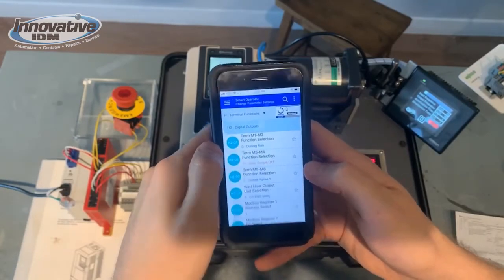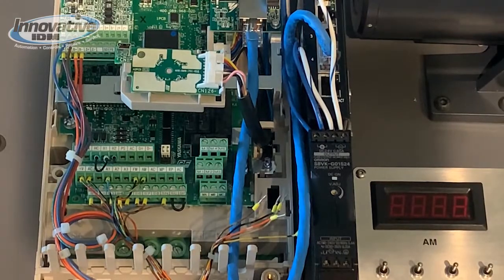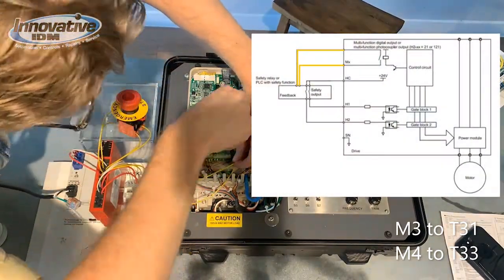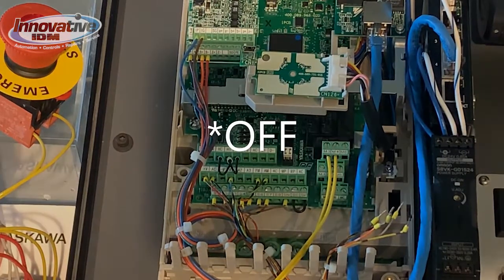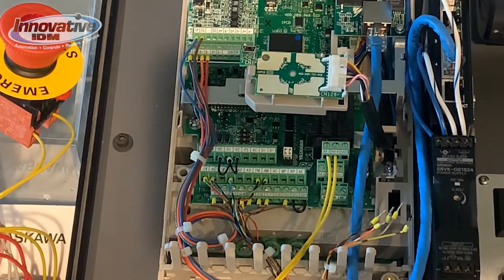Now it's time to wire. Here you can find terminals M3 and M4. Here on the drive we can see our Safe Torque Off inputs — as you can tell, they're jumpered together. If you set this drive up for Safe Torque Off, make sure to not lose that jumper, as the drive won't run without a connection between those three terminals.